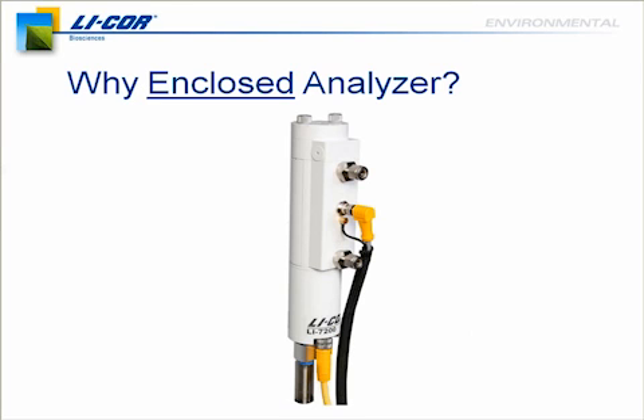I'd like to start by explaining what we mean by enclosed analyzer. The LI-7200 is what we call a compact enclosed gas analyzer, and it's really been based on the LI-7500 platform. We essentially designed this instrument to enclose the 7500's optical path, and that allows us to build on the benefits of the 7500, but also incorporate closed path benefits as well.